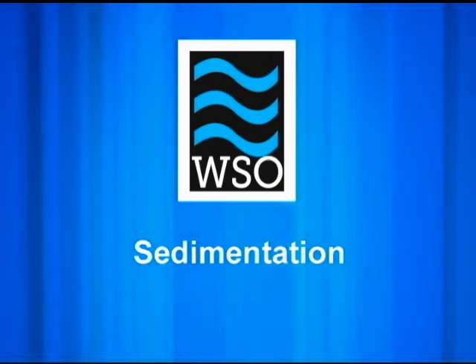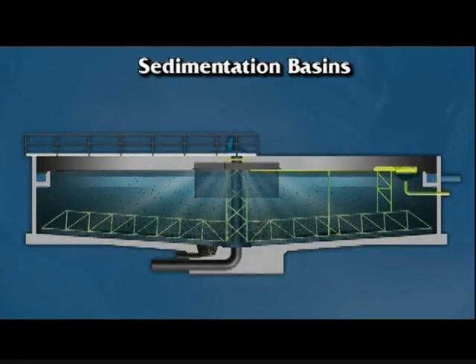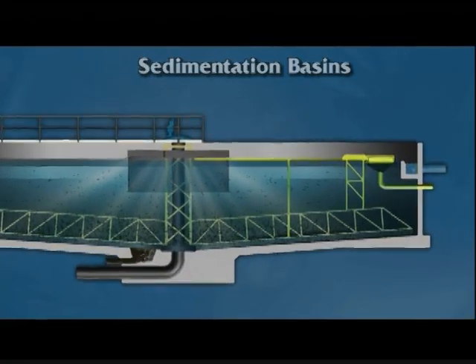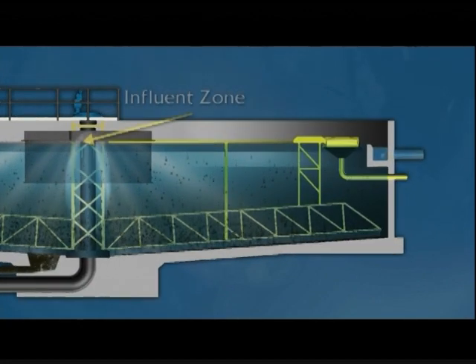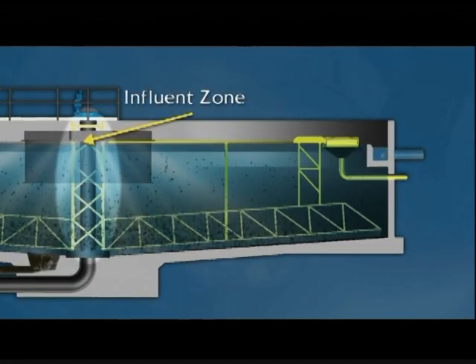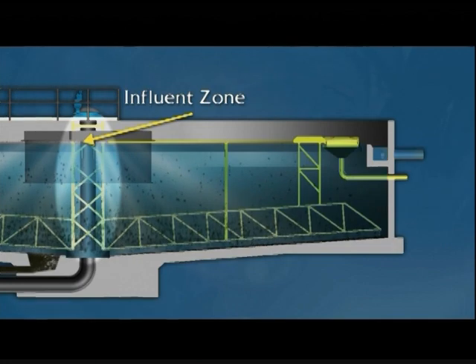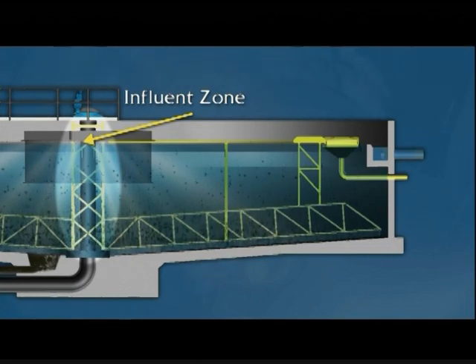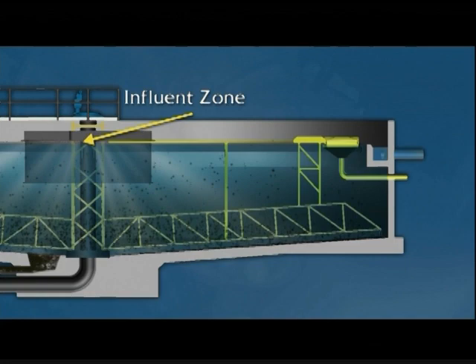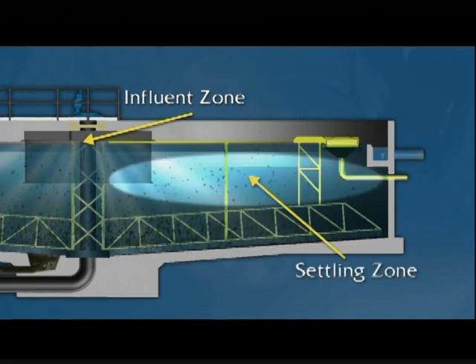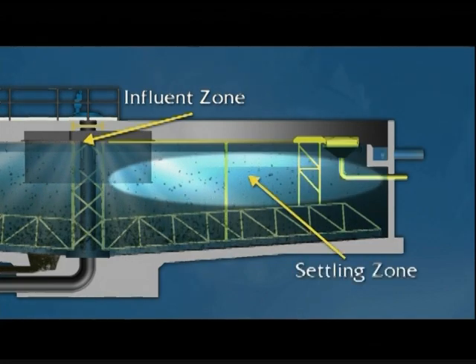Traditional sedimentation basins have four zones. One, the influent or inlet zone decreases the velocity of the incoming water and distributes the flow evenly across the basin. Two, the settling zone provides the calm area necessary for the suspended material to settle.